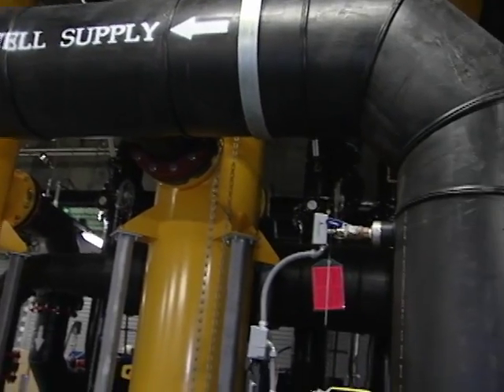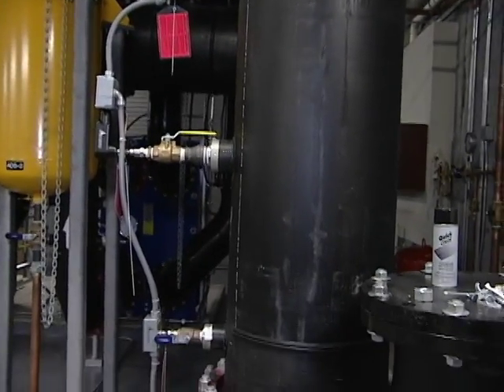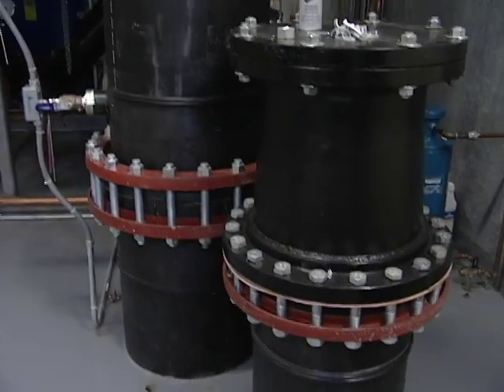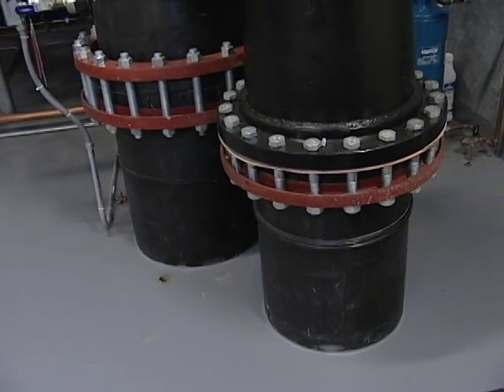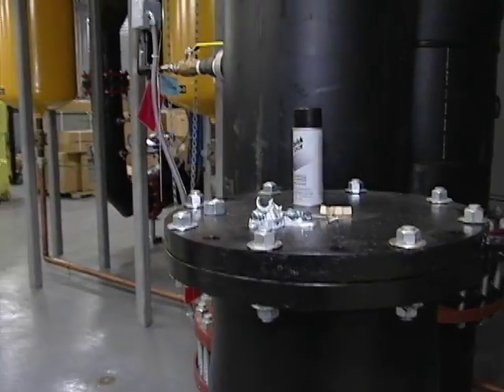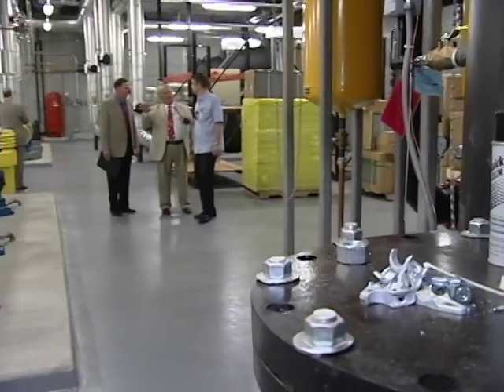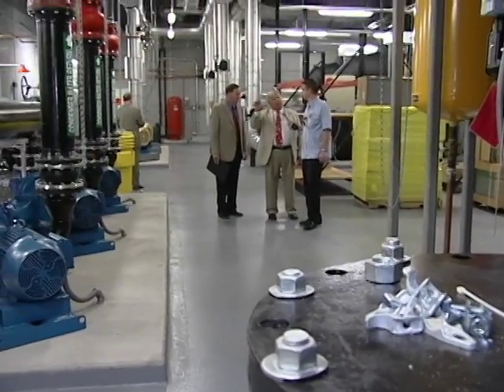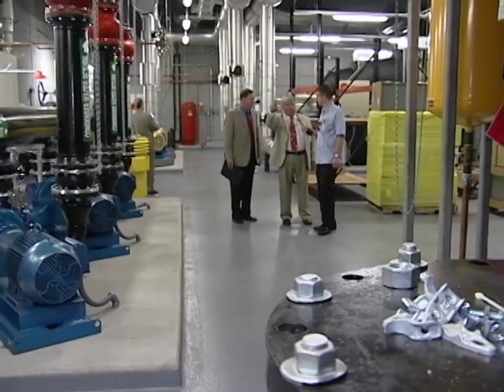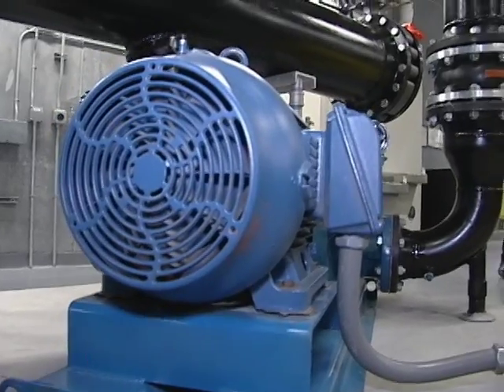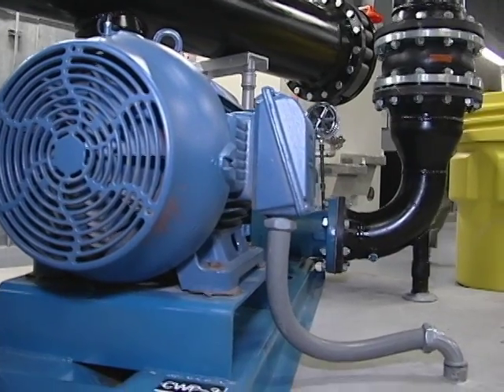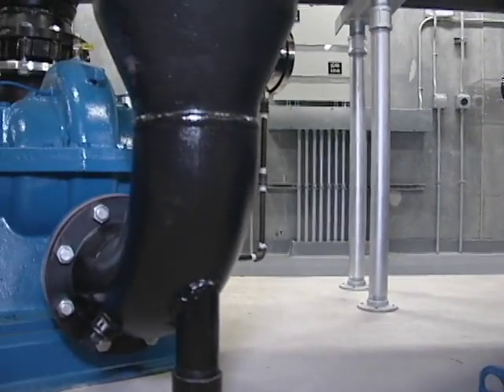Cooling not only the data center, but the whole complex, is a water and money-saving geothermal system that takes the place of traditional water cooling towers. In Florida, cooling towers will spit out $100,000 worth of water a year out of a standard cooling tower. So we take water out of the ground, we put it through a system that just does a heat exchange. There's a couple of plate and frame heat exchangers, and then we put it back into the ground a little bit warmer.